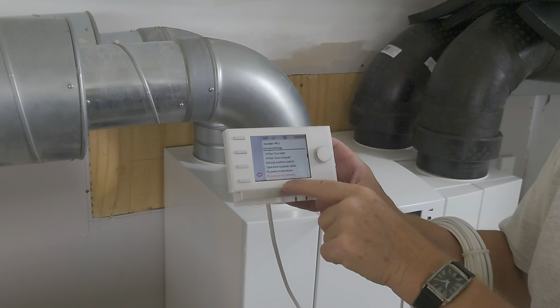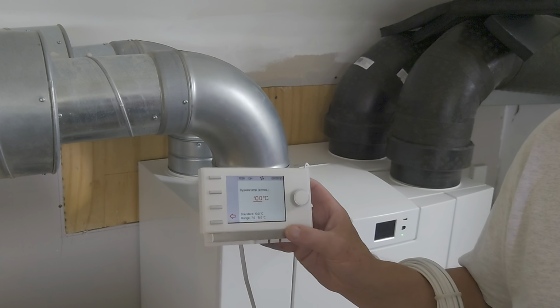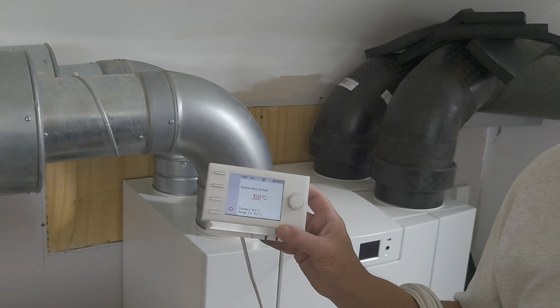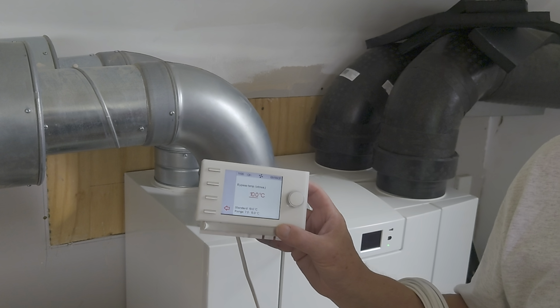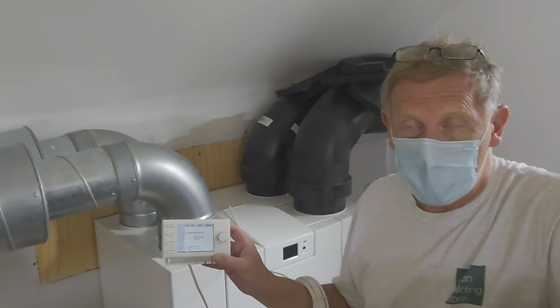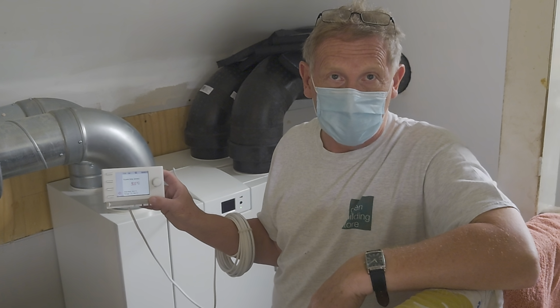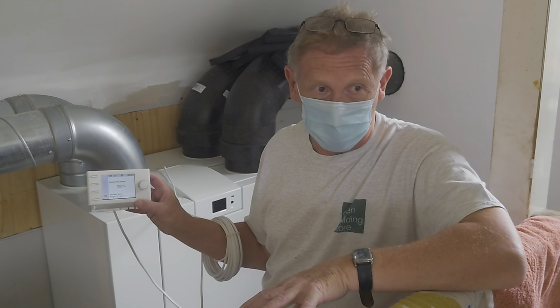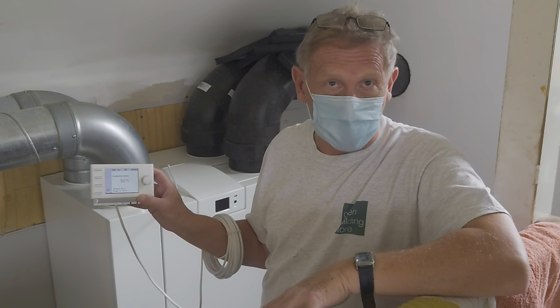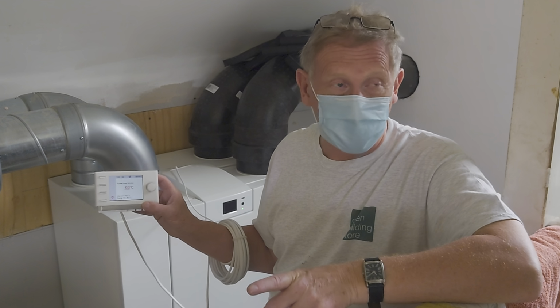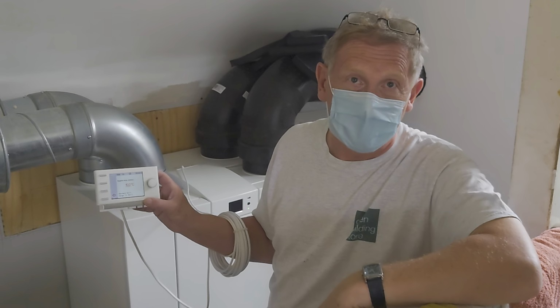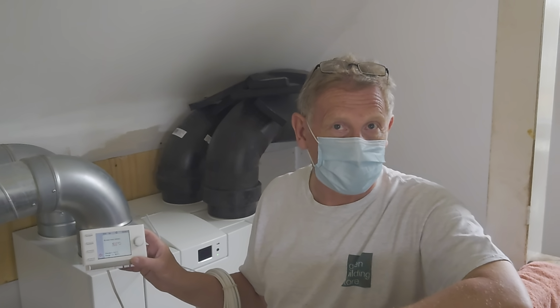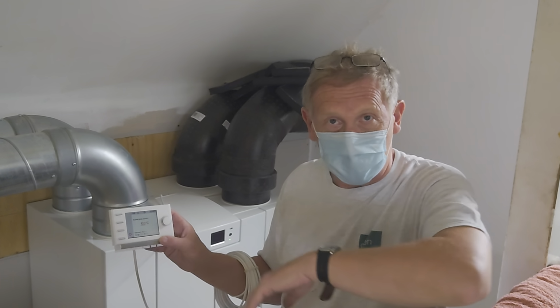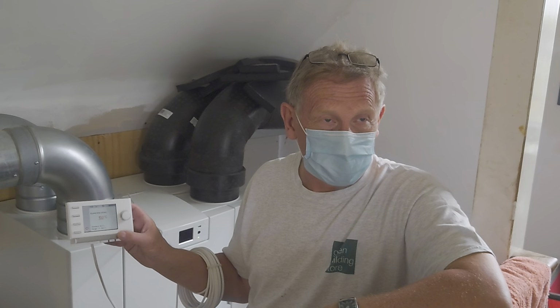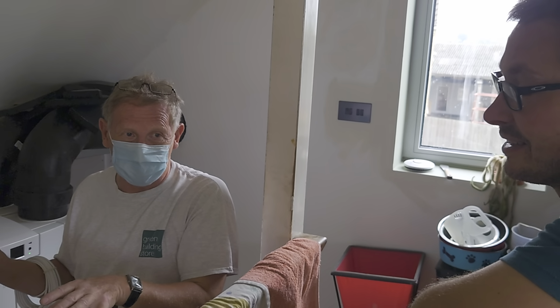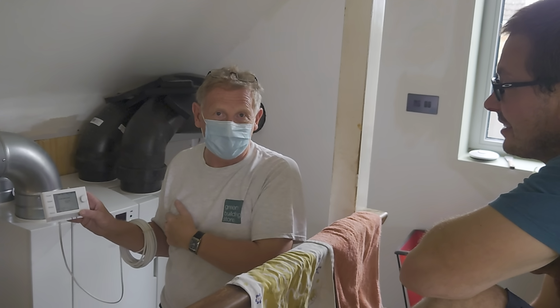The bypass temperature threshold is set at 10 degrees. What that setting means is, if for example we crept above 23 degrees in the middle of winter and it was less than 10 degrees outside, it wouldn't actually go into bypass. So if you had your stove lit, because it was really cold, the machine wouldn't necessarily go into bypass, because it would be bringing very cold air into the house, and if you were anywhere near a supply air valve, you would feel a cold draft. So the bypass does have a lower threshold as well. That's clever. So if it drops below 10 outside, even if you were 30 degrees in here, it wouldn't go into bypass state.